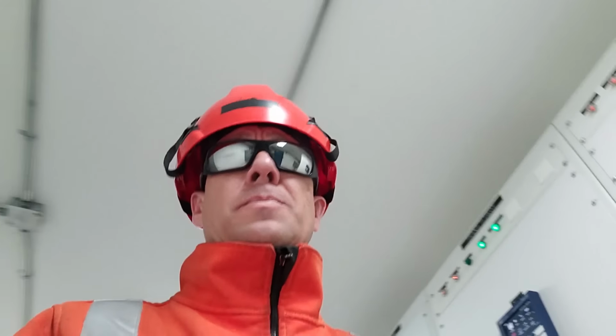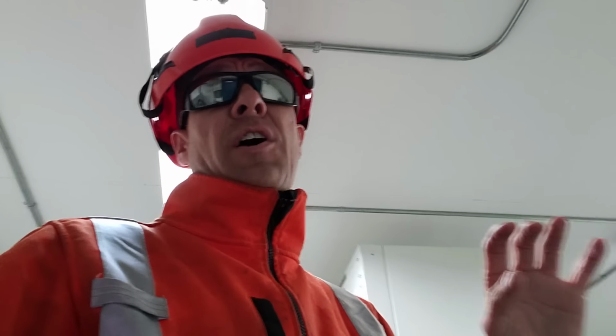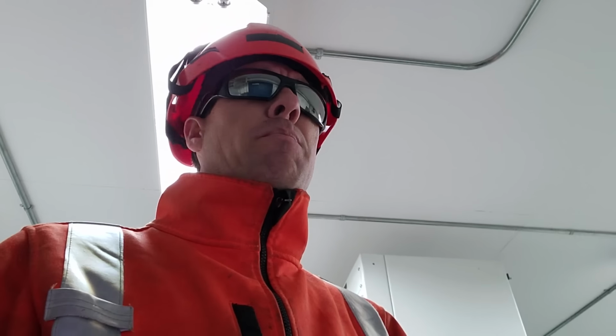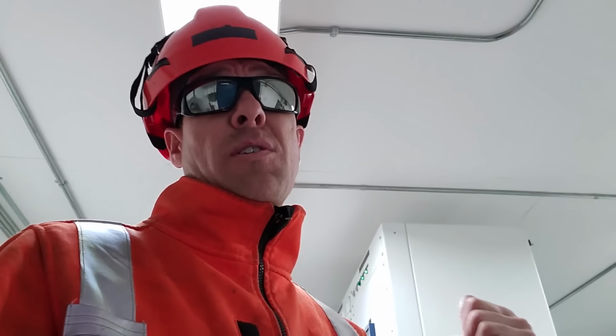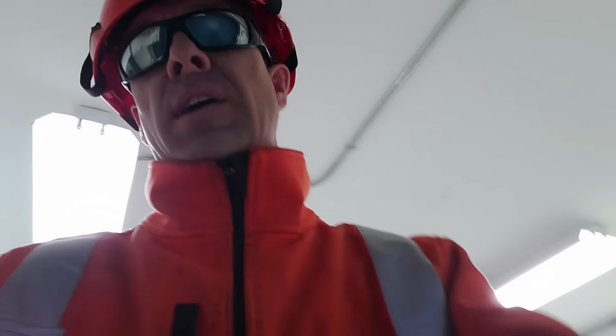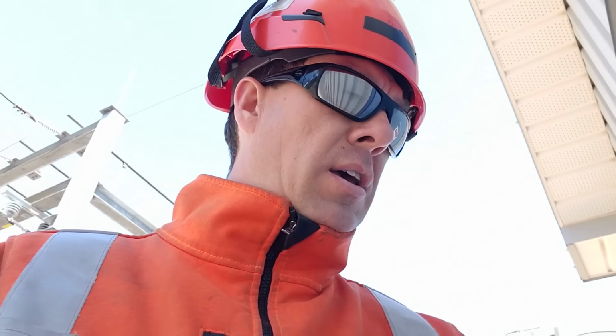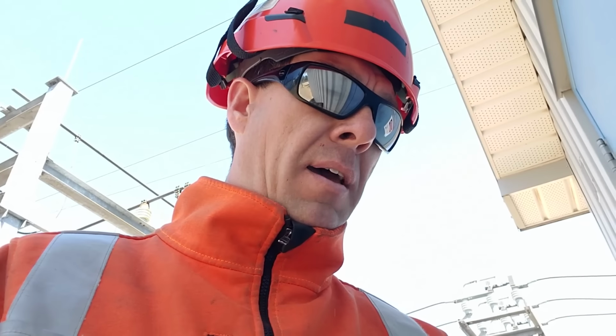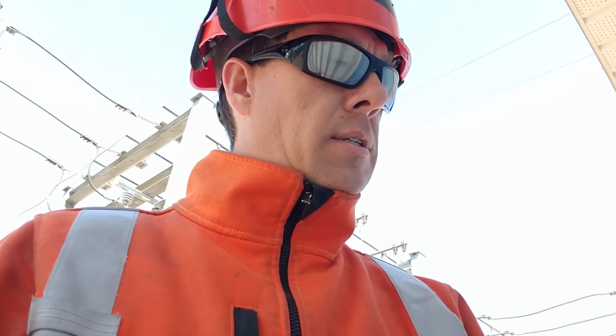Sometimes, if it is a real dry branch, it might hold for 10-15 minutes and then flash over again. In this case, where we found really good evidence that we did find the problem, it made sense. It wasn't in the same direction as what our dispatcher predicted. However, it predicts the distance from the sub. So if we were 13 spans from the sub in the opposite direction, I was still about 13 spans from the sub. It wasn't too far away. That and the branches that were all burnt, and the fact we closed her in and we're only seeing 100 amps, we got her beat. So that's 770 or 780 customers, power restored in 25 minutes flat from the time the power went out. It's a good day. Today is a good day.